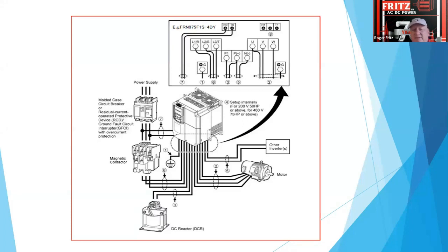And this is the main power circuit. So you've got your 3-phase here. This is actually the DC positive, and I'll go into why they do that in a minute. Then you've got your U, V, and W output, which is your 3-phase to the motor. So that's really your input, and then you have the power to the control.